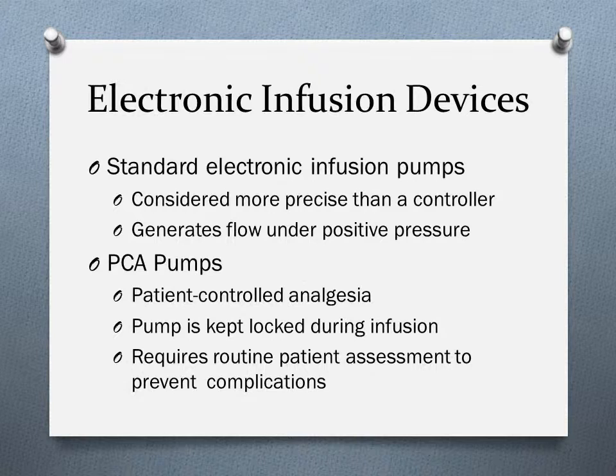It's critically important to know if the pump has free flow protection capability. In other words, is it going to prevent the fluid from just running in, or is it going to allow the fluid to run in without stopping it? Don't rely on the pump alarm to detect IV infiltration or extravasation. It will let you know when there's a problem, but it doesn't always let you know when there's a problem.